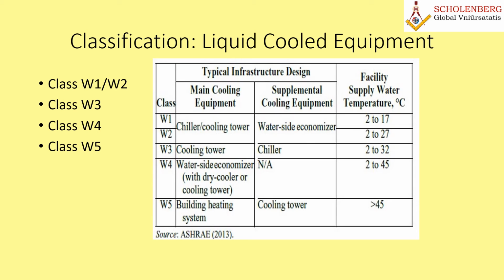The availability of datacom equipment rated for class W3 to W5 is very limited. It is anticipated that future designs in this class may involve a trade-off between IT cost and performance. However, these classes allow lower cost data center infrastructure in some locations. The facility water flow rate requirement and pressure drop values of the datacom equipment may vary.